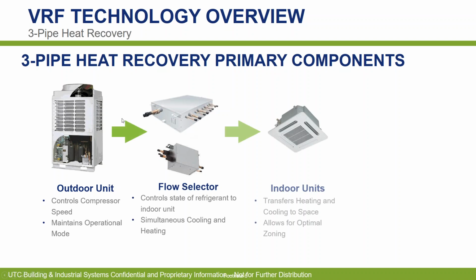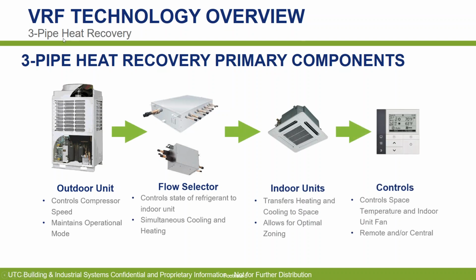Heat recovery, and this is where we get into our 3-pipe layout. So it's no longer just a liquid and a suction line, right? So we've got a liquid, a suction, and a hot gas line. That's where the whole 3-pipe terminology comes from. Our outdoor unit here, as mentioned previously, flow selector boxes, indoor units, and our wall controller.